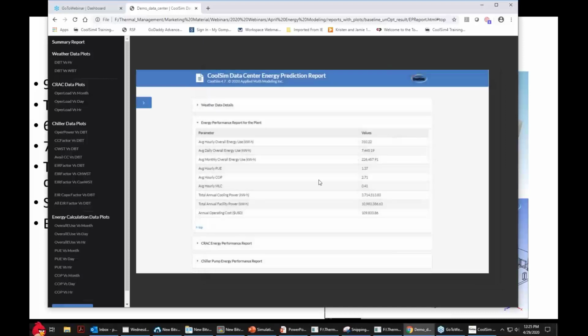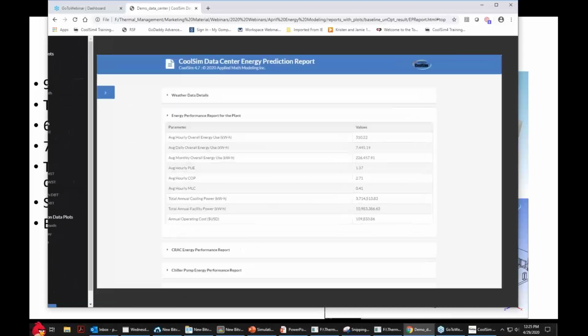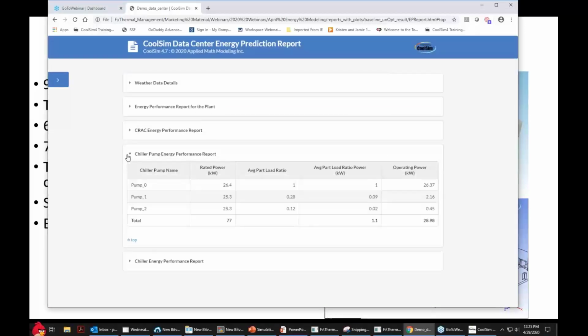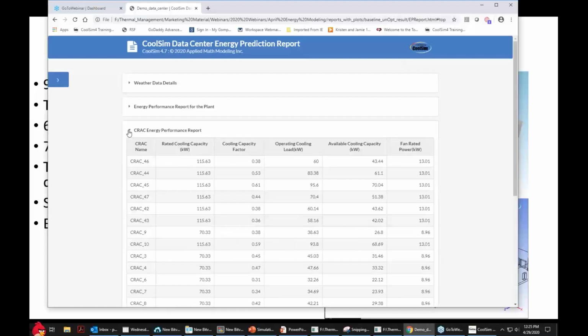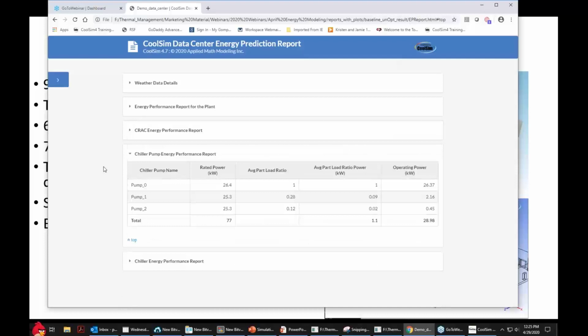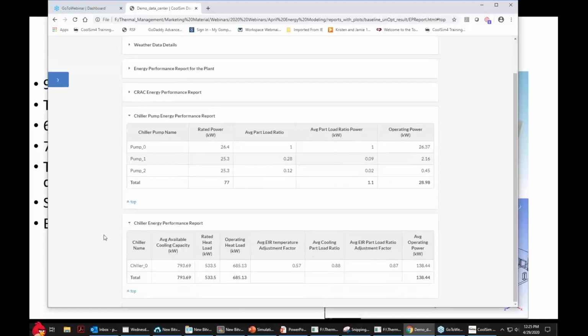Okay, so we have all these plots, and this will all be part of the output report. Chiller pump efficiency here. Here's the performance of the pumps. This is their rated power, part load ratios, the CRACs. Here is the energy performance of each of these. They're labeled CRAC, but it's really an air handler because this is a fan coil in the room. And so all of the data that you could possibly need. Here's chiller efficiency.